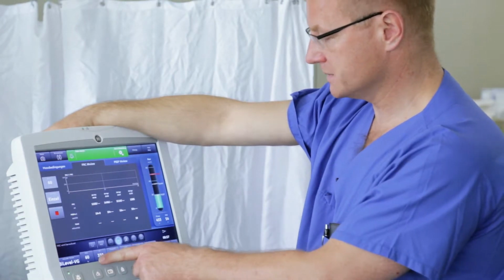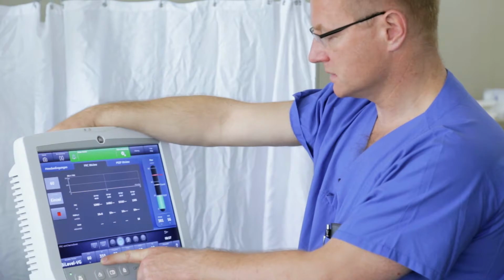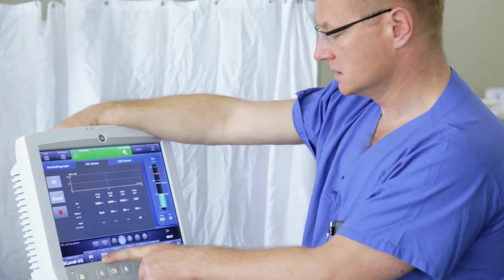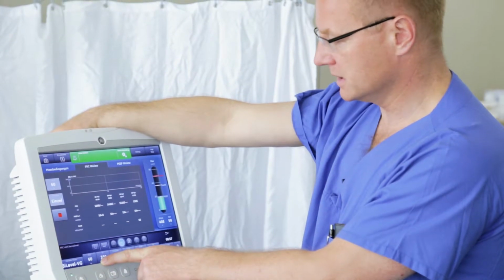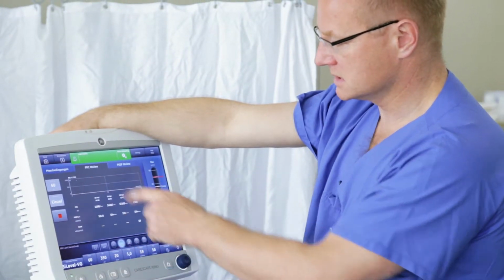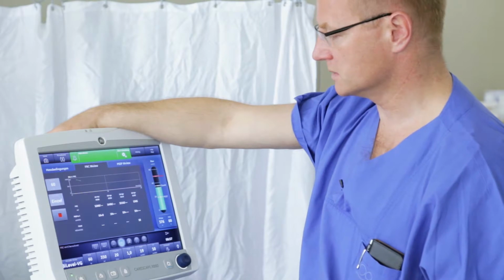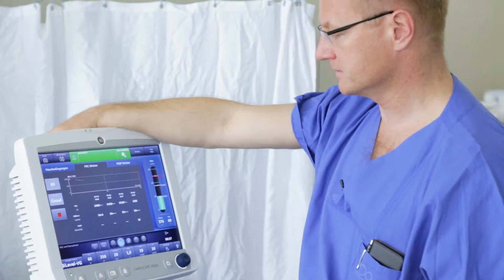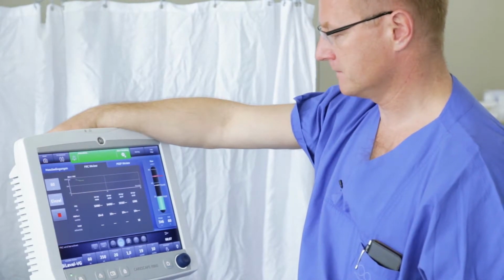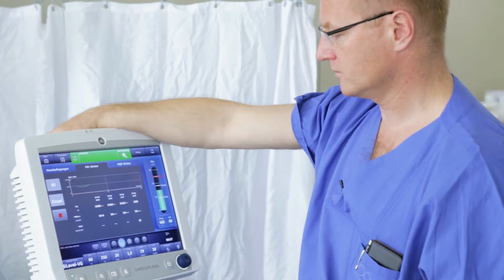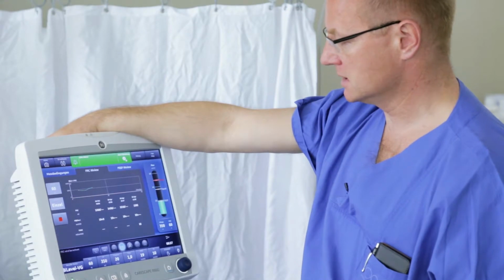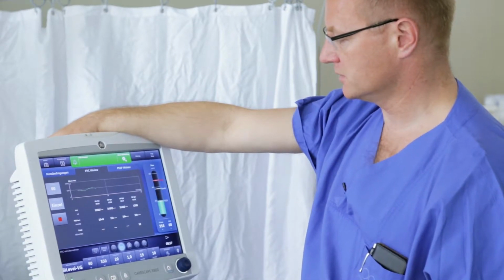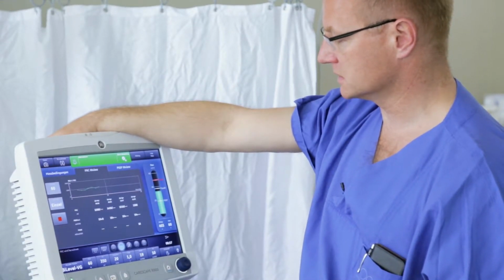Down here you can see that the device has now changed the inspiratory oxygen concentration from 50% to 60%. Thus the measurement is about to begin, and here we already have the first measured value, which is displayed as a green dot. It will now be approximately 20 to 25 breaths before the inspiratory oxygen concentration has finally increased to 60%.